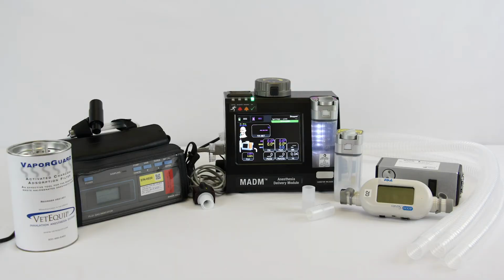To complete operational testing, you will need an adjustable flow source, the power cable and adapter, patient sensor circuit adapters, a flow meter, an external anesthetic gas analyzer, 4 pieces of patient tubing, at least 25 milliliters of liquid anesthetic, and a charcoal absorption filter.